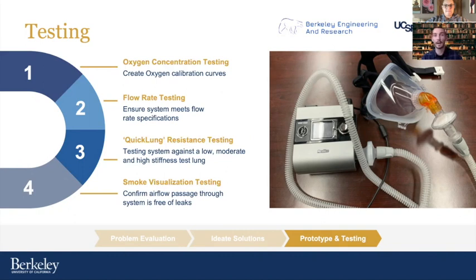The first of which was oxygen concentration testing. So using the facilities of a Berkeley alumni, we were able to use the Berkeley Engineering and Research facilities just down the road in Berkeley, where I live. And we were able to use his facilities to test the oxygen concentration when we added oxygen into the flow of the system. So using that test method, we were able to create essentially a calibration curve, or like a manual that a doctor would use if they were trying to help a patient. And it would say, doctor, you need to provide this much oxygen into the system if you want to get this output amount of fraction of inspired oxygen to your patient. So we included that essentially in our assembly instructions for the system.